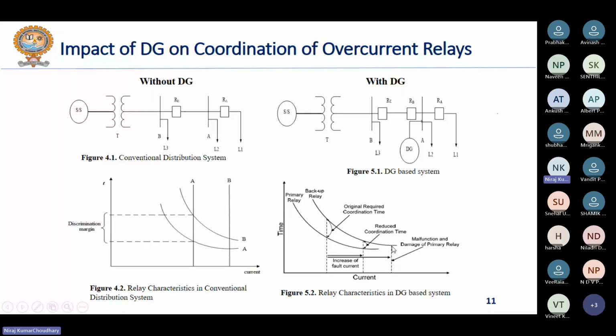And even in some cases, the time of operation of the backup relay will be less than the time of operation of the primary relay. So in that case, this is a violation of the relay coordination, that your backup relay operates prior to the primary relay operation. That we will see in the result section.